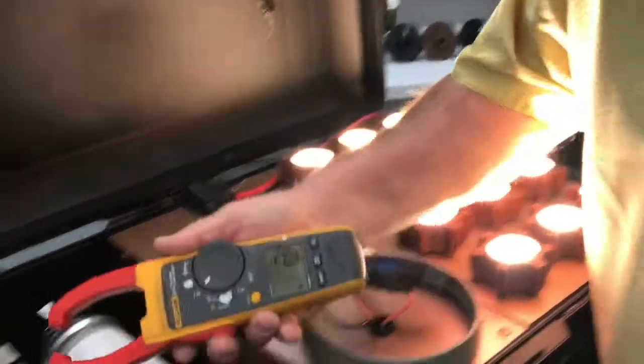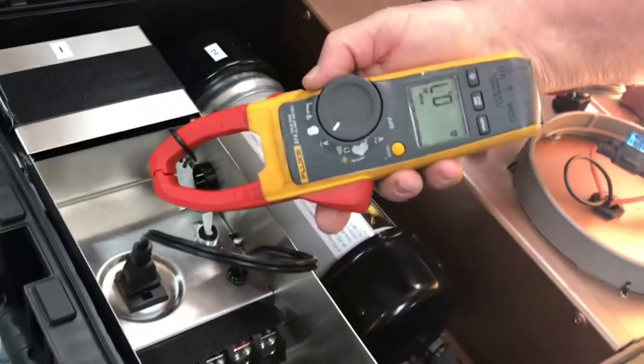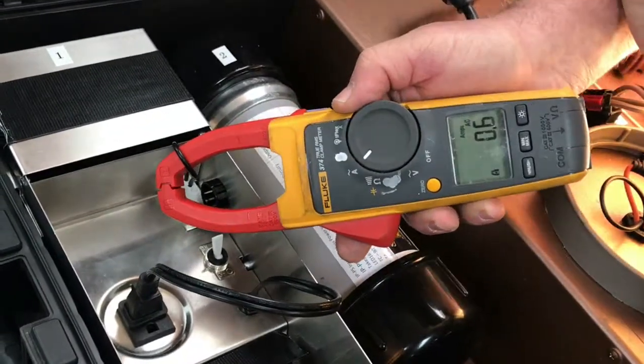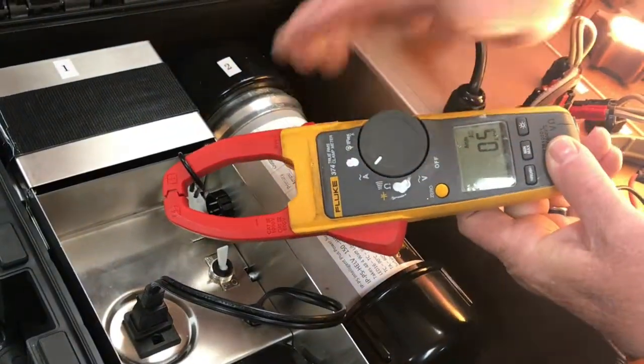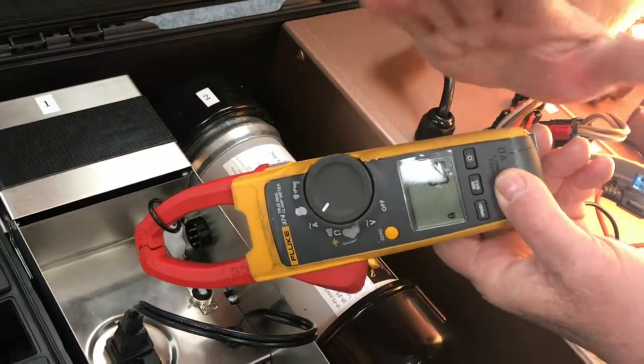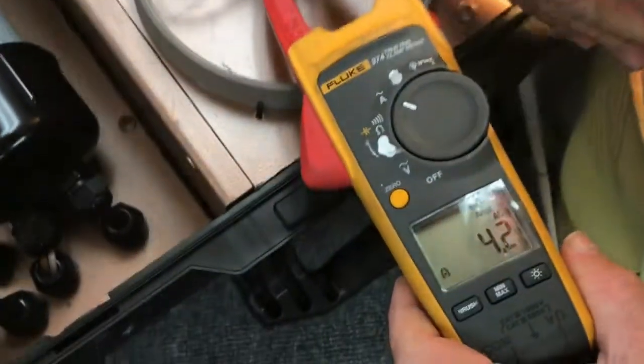Now I'm going to take an amp probe and take a reading of the primary amps. You're going to see that the primary amp reading is 0.6. I'm going to come over here to the secondary and take an amp probe reading, and you're going to see that it says 4.2.